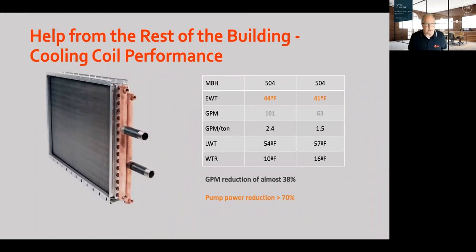So you can get help from the rest of the building through your cooling coil performance. You can have lower flow with the lower chilled water and increase the energy savings that way. Heating coils are often fairly old in a lot of hospitals, depending on where you're working right now, but those can get fouled up and they can be the source of pressure drop that's requiring you to run your 100 or 200 horsepower pumps in the main plant at full speed, rather than being able to slow those down, which is a substantial amount of energy.